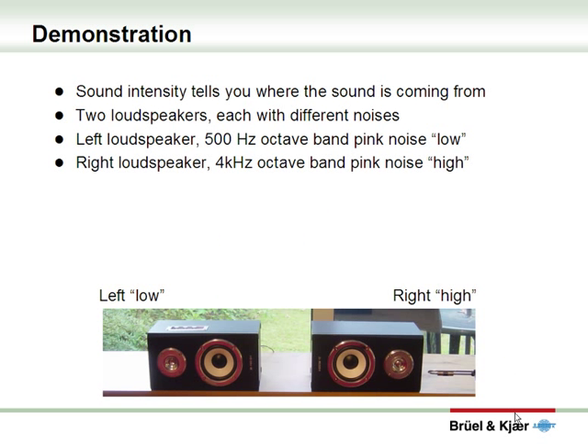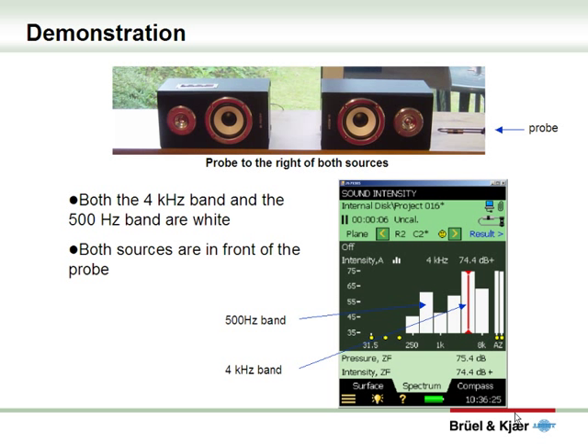Let's look at the demonstration measurement performed earlier. Sound intensity will tell you where the sound is coming from. In this demonstration there are two loudspeakers, a left and a right. The left loudspeaker gives a 500 Hz octave band pink noise, and the right gives a 4 kHz octave band pink noise. When played together they mingle, but come from two different sources. If we place the probe to the right of both loudspeakers, the sound from both speakers passes the probe in a positive direction, colored white on the instrument display — so both the 500 Hz band and the 4 kHz band are white, showing both sound sources are in front of the probe.